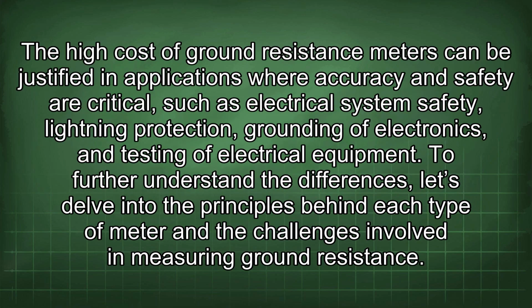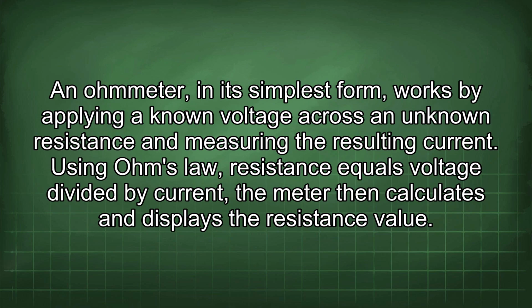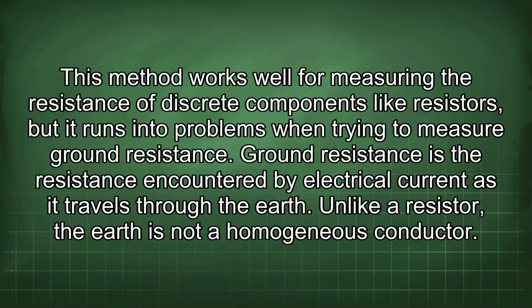The high cost of ground resistance meters can be justified in applications where accuracy and safety are critical, such as electrical system safety, lightning protection, grounding of electronics, and testing of electrical equipment. To further understand the differences, let's delve into the principles behind each type of meter and the challenges involved in measuring ground resistance. An ohmmeter, in its simplest form, works by applying a known voltage across an unknown resistance and measuring the resulting current. Using Ohm's law, resistance equals voltage divided by current, the meter then calculates and displays the resistance value. This method works well for measuring the resistance of discrete components like resistors, but it runs into problems when trying to measure ground resistance.